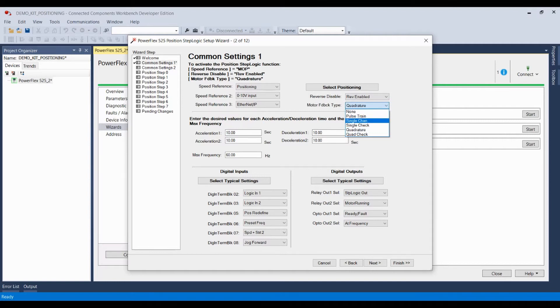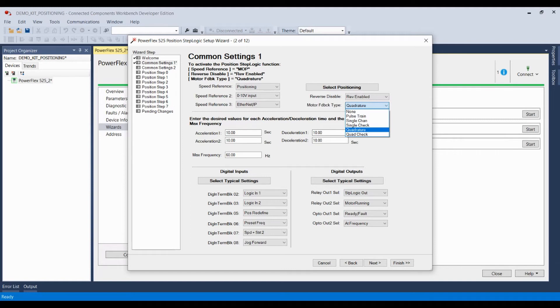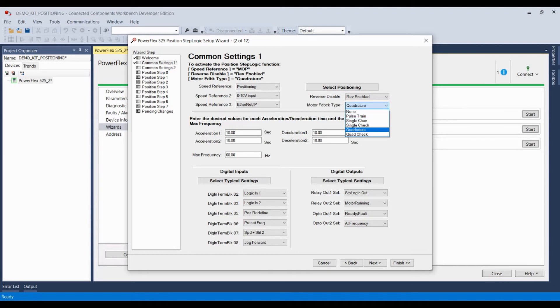Now, I happen to have a quadrature encoder installed on my drive, and if you're going to use simple positioning, you must either have a quadrature or quad check encoder. If you're going to engage in velocity step logic, you can use any one of these options, including none. But for positioning, you need quad or quad check, and today we have a quadrature encoder, so we're going to select that.